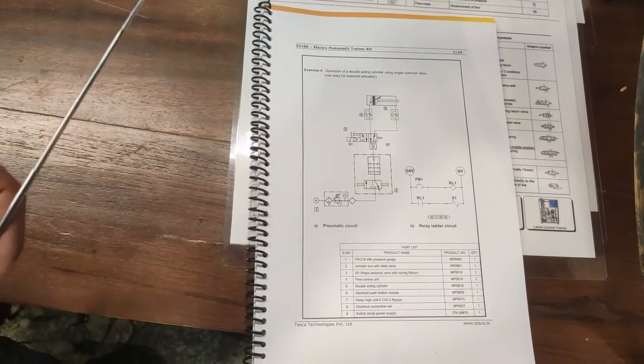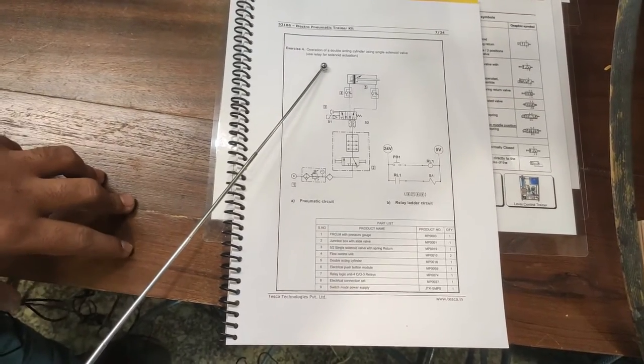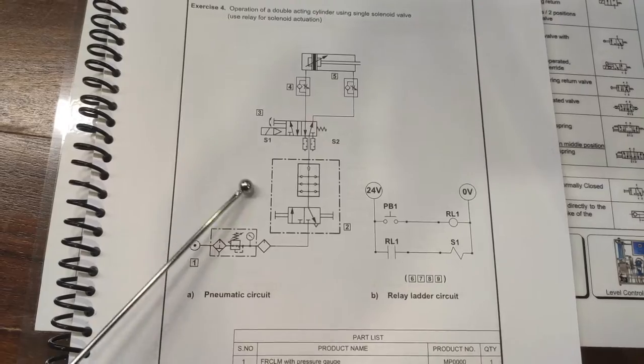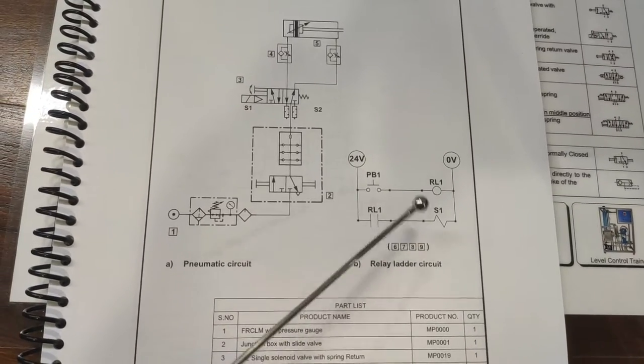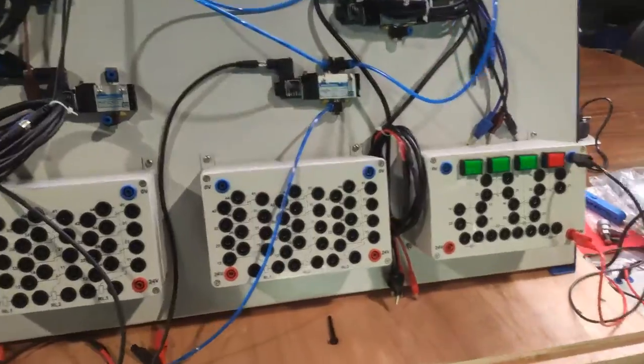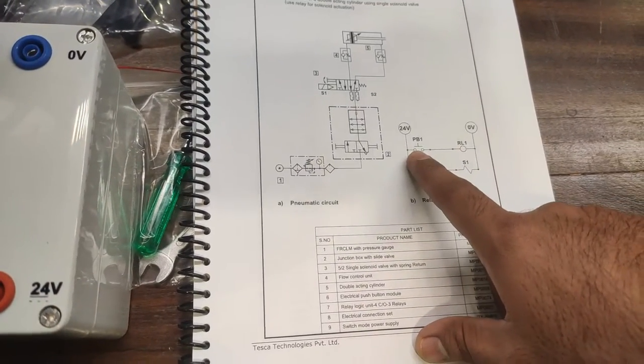Exercise 4: operation of a double-acting cylinder using a single solenoid valve, but now using a relay for solenoid actuation. In the earlier exercise we directly operated the solenoid valve using a push button. In this case, the push button first operates a relay, and then the relay operates the solenoid valve. The pneumatic diagram remains the same as the last exercise for the double-acting cylinder; only the electrical circuit changes to include a relay.